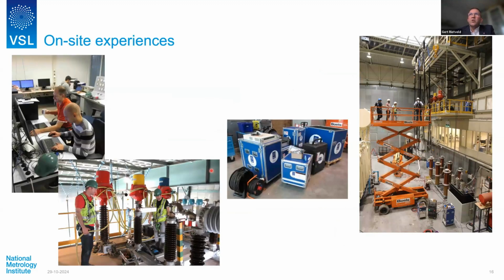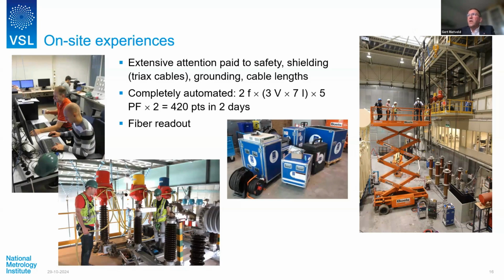I'll conclude by showing you some on-site experiences, my colleagues making up the current circuit, implementing here, putting our equipment high up. You see here a power transformer, and you can also get an indication of the scale of such a high voltage laboratory. It's extremely high. Equipment is here, so it's a special environment to do the calibration. And you also see that the cables are really non-negligibly long. We typically have 10, 15, 20-meter cables. And moreover, it's in an industrial environment.